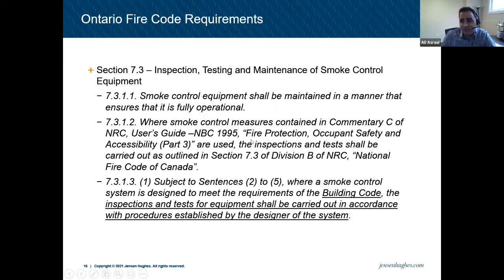It is safe to say that this is basically SB-4. So all these things that you see, these measures in that NRC user guide, SB-4 is written based on this. So basically, we can say if we have measures from SB-4, the inspection and test shall be carried out as outlined in 7.3 of Division B of the National Fire Code of Canada. When we go to 7.3 of the National Fire Code, there are certain test and maintenance procedures for these systems. So basically, if you have a measure in your building, you've got to follow National Fire Code requirements.